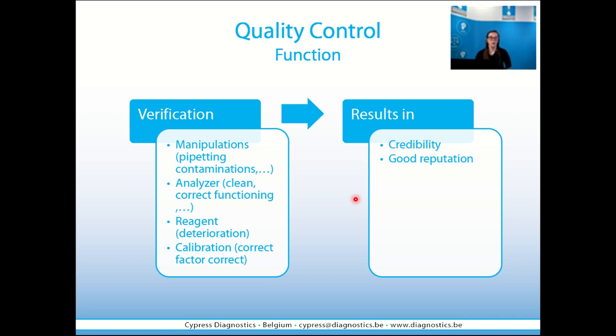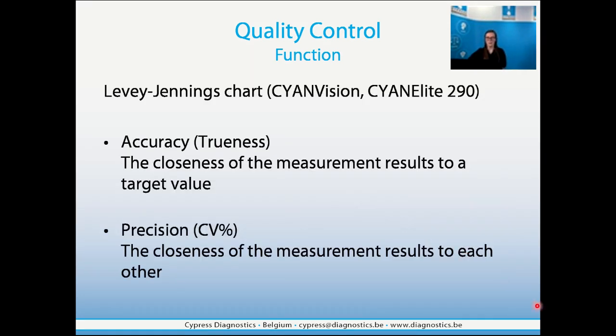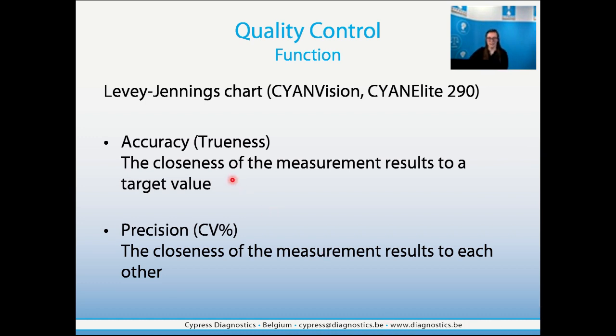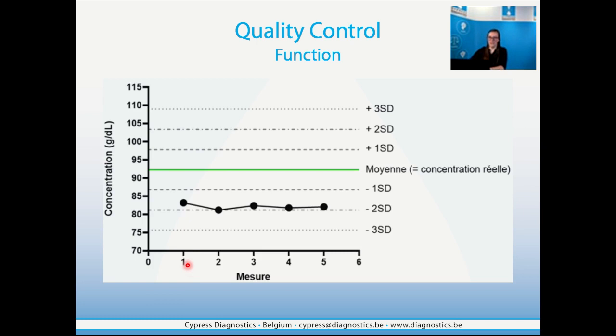What is the consequence of not doing quality controls? You have no proof that the patient results are reliable. How can we monitor quality controls? In our newest systems like the Cyan Vision and Cyan Elite, we use Levey-Jennings charts. Levey-Jennings charts are used to monitor the accuracy and the precision of quality control measurements. Accuracy looks at the closeness of measurement results in comparison with a target value. Precision, on the other hand, looks at the closeness of measurement results in comparison to each other. Let's look at a Levey-Jennings graph to make things easier to explain.